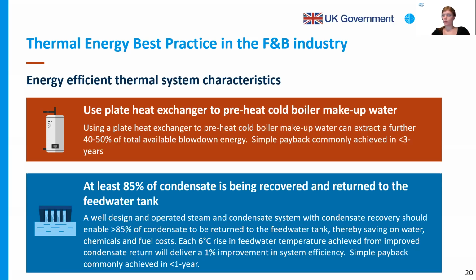And condensate recovery systems that allow for recovery of at least 85% of the condensate as a best practice to the boiler feed water tank is critical, not just for fuel economy, but also for water economy, and also for saving chemicals that are added. So rule of thumb is that every 6 degrees increase in the boiler feed water temperature achieved from condensate return, or if you achieve boiler feed water increase by economizers also, it will deliver a 1% increase in the boiler system efficiency. And simple payback is actually quite short, in a matter of a year or two.